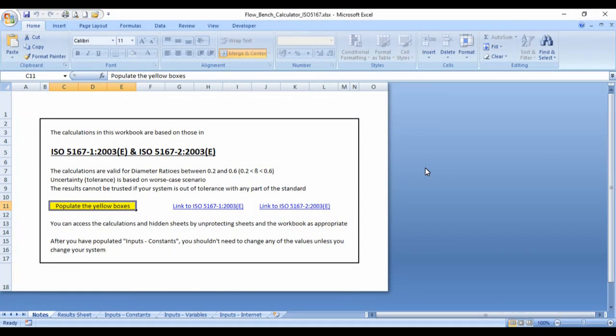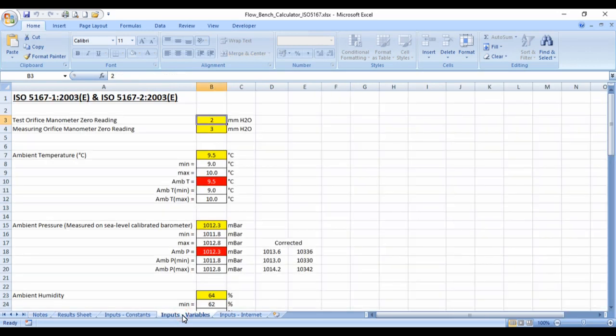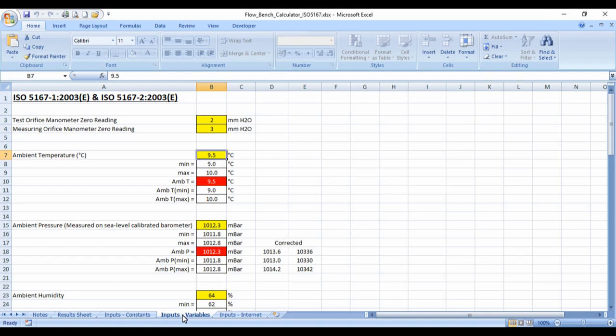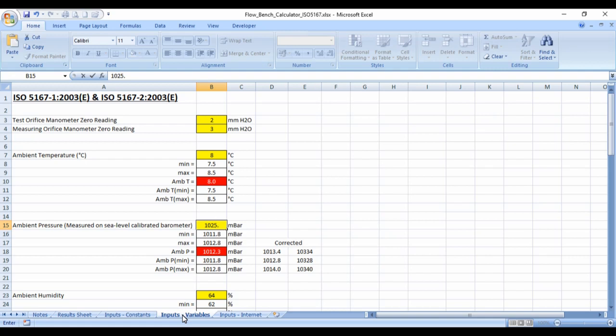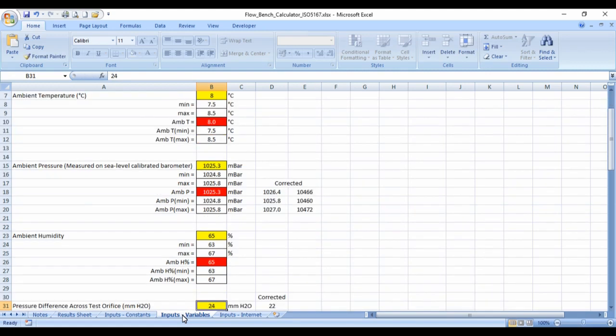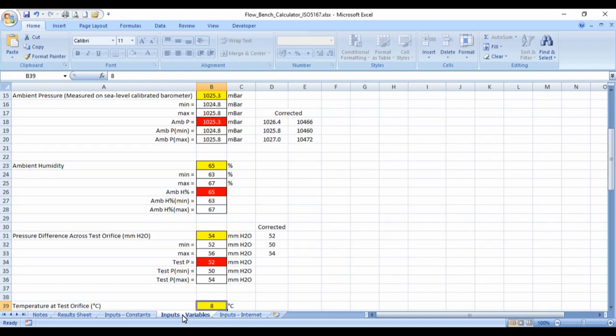Using the spreadsheet that I've created, we'll now input the variables. These first two are zero readings on the manometers. Ambient air temperature, 8 degrees. Pressure was 1025.3. Humidity was, I don't think I took the humidity, but we'll guess the humidity at 65. Difference across the test manometer was 54 millimeters. Temperature to test manometer was 7.1.